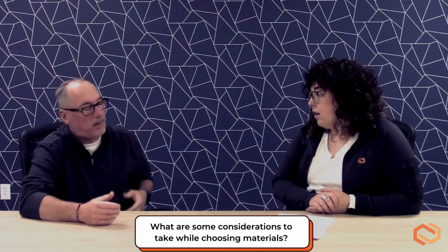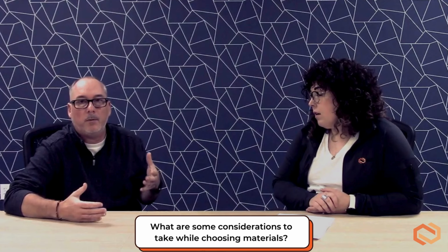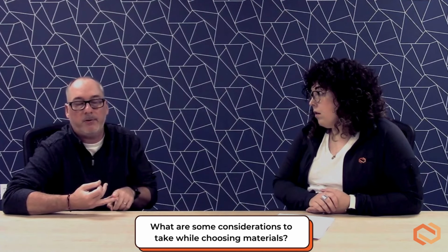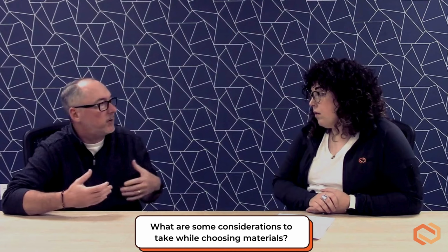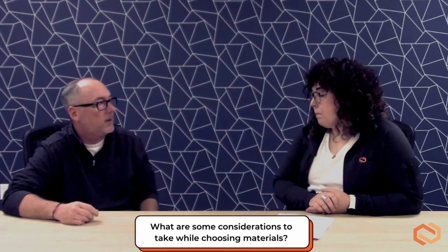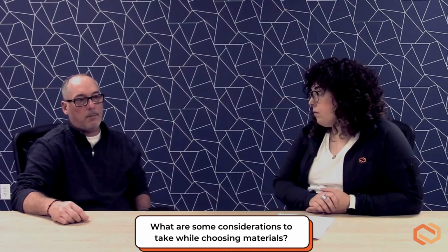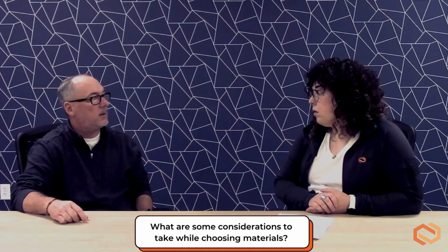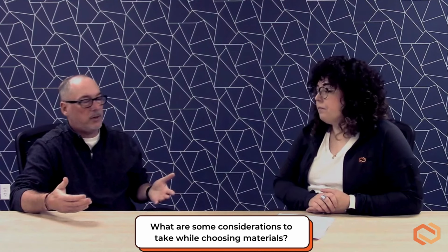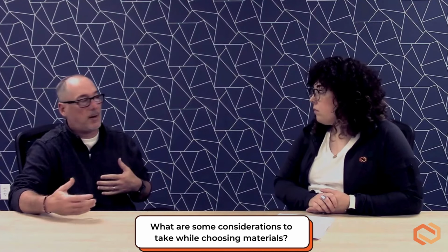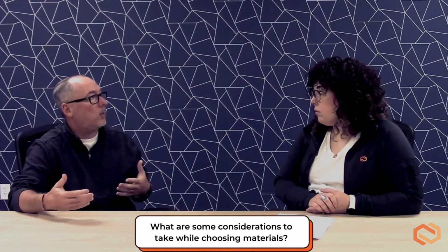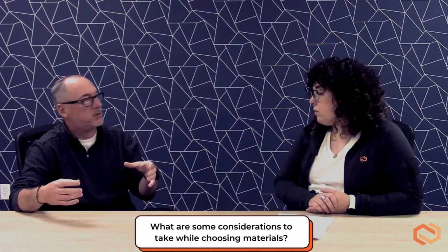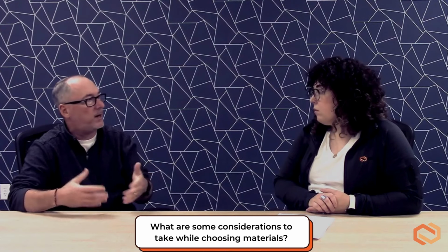Absolutely. So from my perspective, it all boils down to the product itself, what type of product you have. Mass and geometry are probably two of the key attributes that you need to look at in choosing the right package to encapsulate it. For example, if I've got a multi-material product that's got a lot of sharp edges or points on it, then I'm not going to want to put this into a pouch. It should go into a tray. Or if I'm dealing with a product that's got a lot of mass, again, I really don't want to put that inside of a pouch just for that reason. A mass inside of a pouch is like a projectile versus putting it into a tray to try to encapsulate it a little bit further.